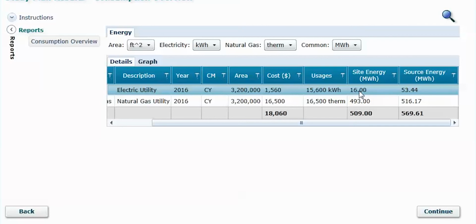So what we want is to be able to compare those numbers. Hopefully they are reasonably close, and even beyond that, more importantly, we should be able to explain the differences. If we're looking at a section of buildings that includes a lot of warehouses, we'd expect to be under that average. And we'd expect to be under the average as well because that average included things like street lighting and other aspects. If we have a very high energy density group of buildings that we're looking at with computing centers and things, we'd expect to be above it. So those are some of the things that just get us in the ballpark.